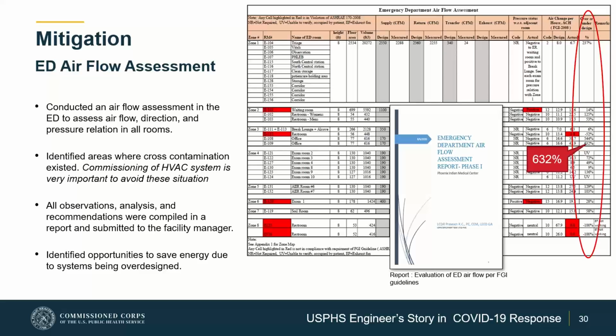I also identified the opportunity to save energy, though that wasn't the intent of this assessment. My calculation showed that this space was not commissioned properly, and in my design you can see some places had almost 600% higher than the design air supply rate or air change rate.